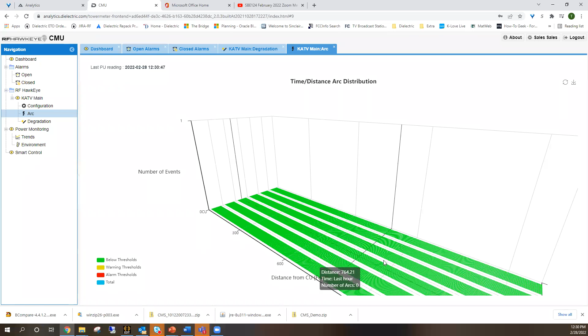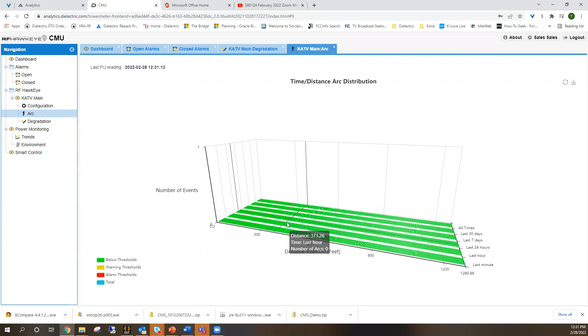And then you can go to this arc histogram. It'll give you, basically, the last minute, the last hour, last 24 hours, 7 days, month, and then all time. And it'll give you the number of occurrences on the Z-axis. And then it'll give you a location marker across the X-axis, if you want to call it. So if you were to have an arc, it would populate up, and then as time progresses, it'll move its way to the back. And it'll show you if it's a warning, it'll be yellow. If it's an alarm, it'll be red.